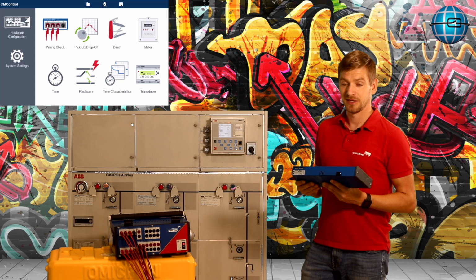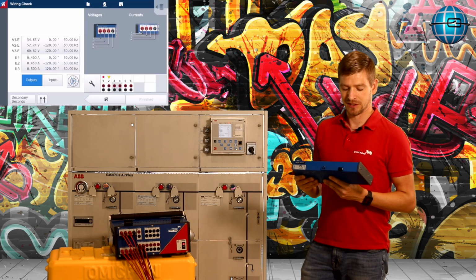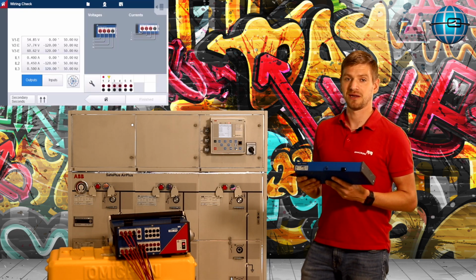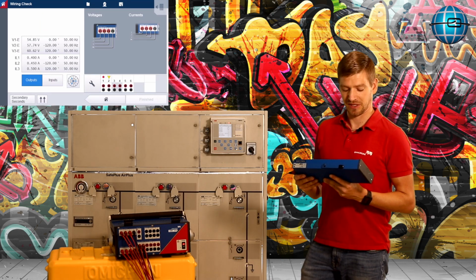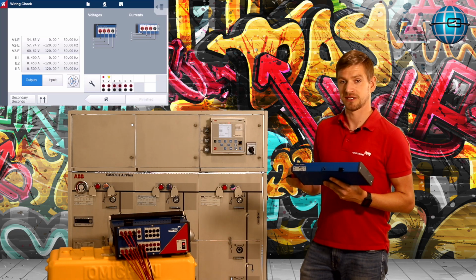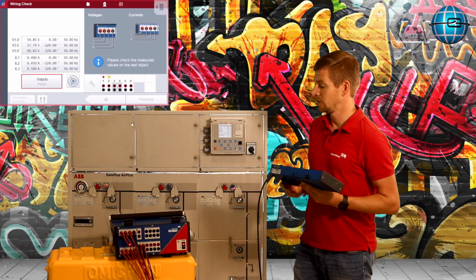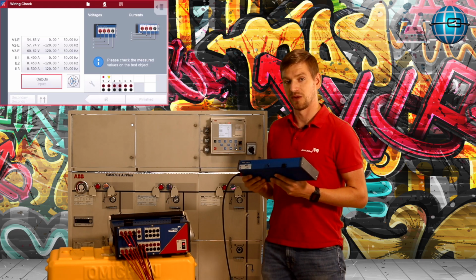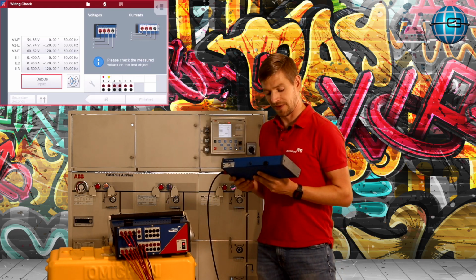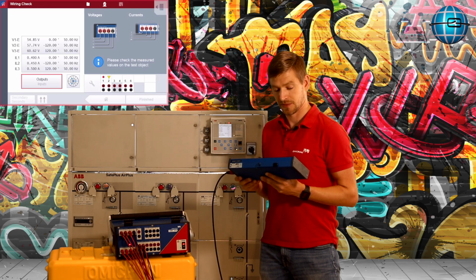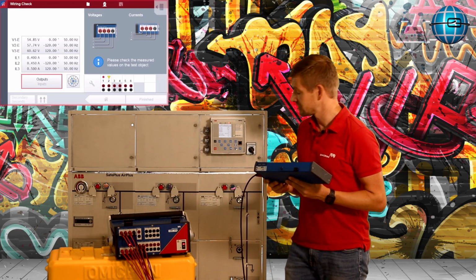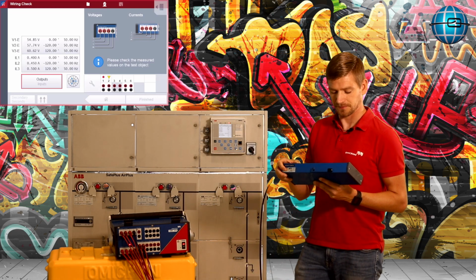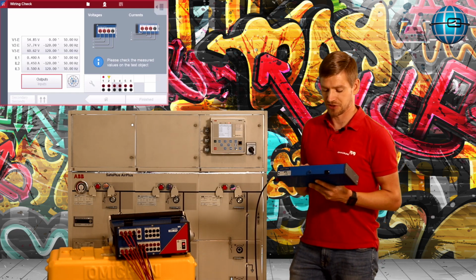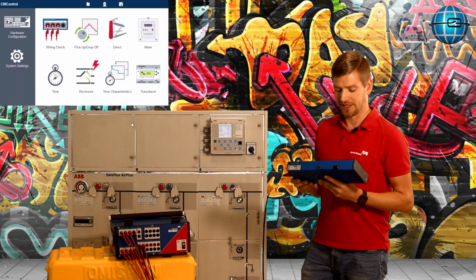So we go up here in the wiring check, and here CM control automatically gives you some symmetric values for the injection. Just by pressing the start button, CMC will start with injection, and we can verify on the front panel the values we are injecting. So everything looks good, the voltages and the currents. Okay, stop injection. And now we would like to start with the pickup and drop-off test.